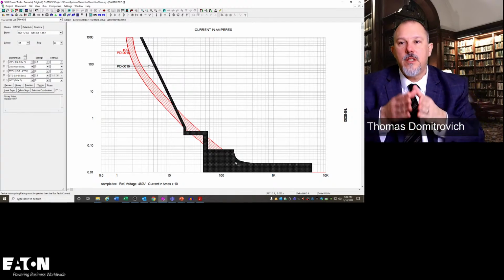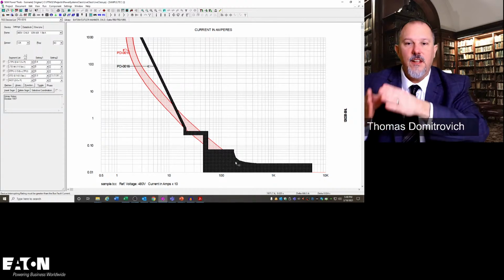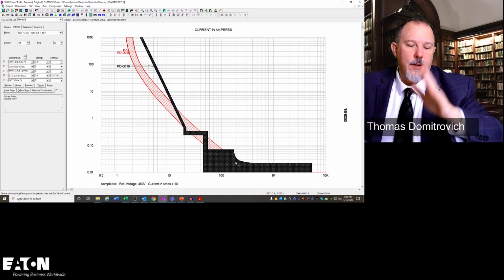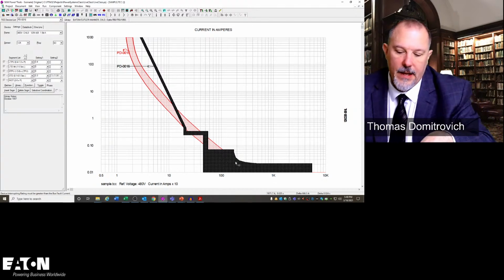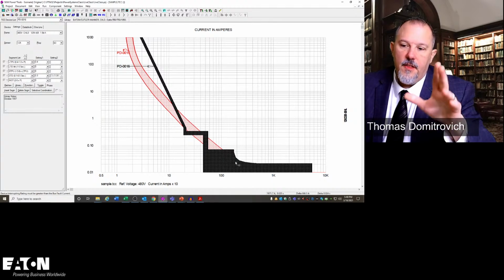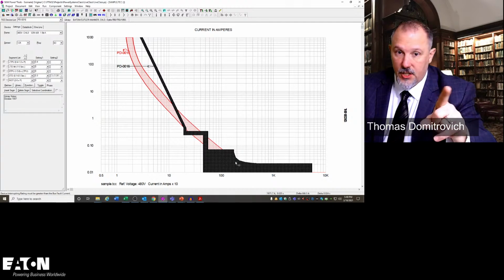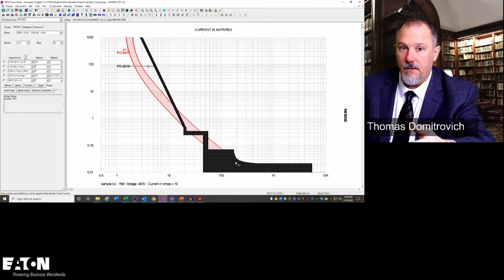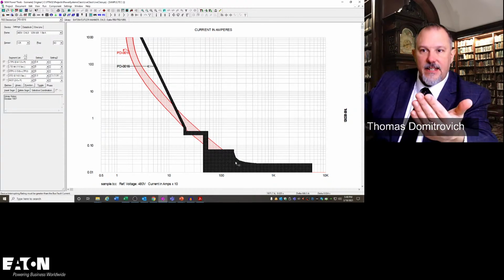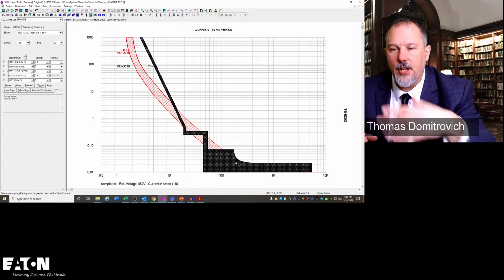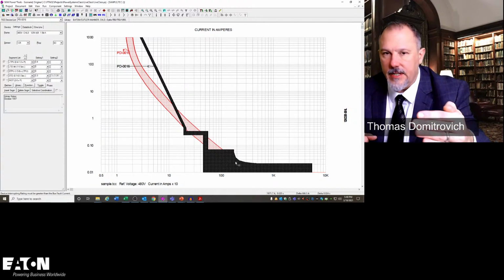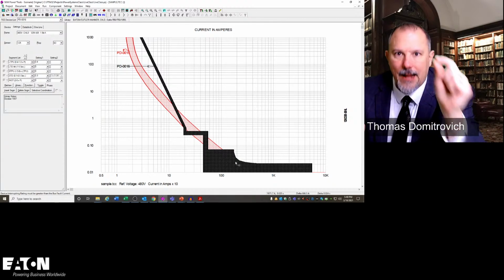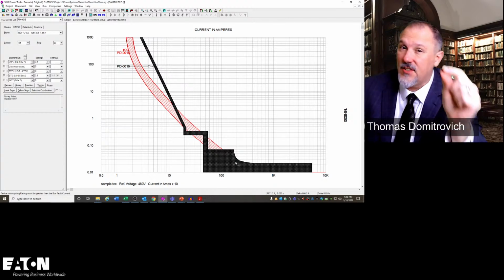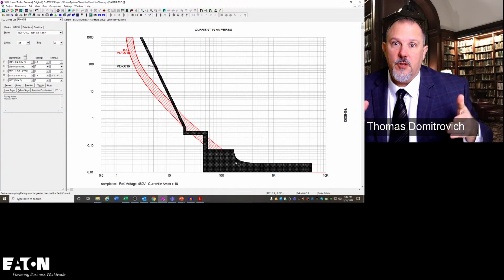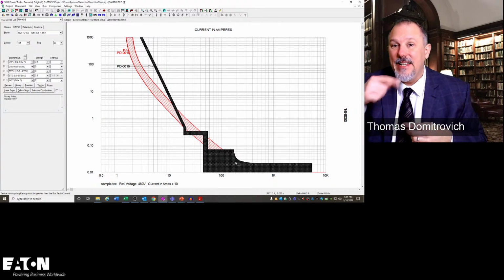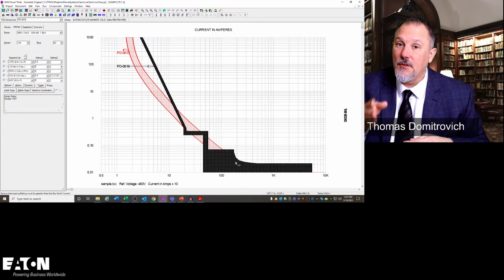Why is that? If you go to the time current characteristic curves from the manufacturer, I'm not going to call one up. We'll just go down another rat hole. If you go to the TCC curves of a manufacturer, you'll find that they'll tell you that these curves are good for 50 and 60 hertz. These curves are good from this temperature to that temperature. They'll give you all these qualifying factors. And you know what we do as engineers? We will publish a longer clearing time. We'll put fatter bands than what is reality, because we don't know if you're using it at 50 hertz or 60 hertz. And sometimes we'll say, I can't plot both of those because the band would be huge. So I'm going to plot it at 60 hertz, but I'm going to tell you on the TCC curve that you need to adjust this if you're using it at 50 hertz.